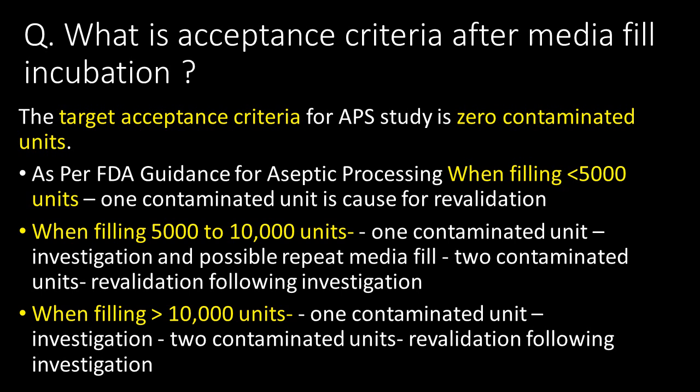Continuing the acceptance criteria: when two contaminated units are found in a batch of 5,000 to 10,000 units, it will cause revalidation following investigation. When media fill batch size is greater than 10,000 units, one contaminated unit will cause investigation, and two contaminated units will cause revalidation following investigation.